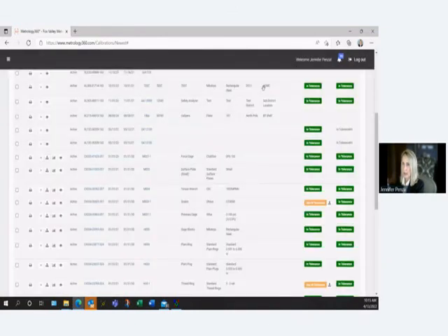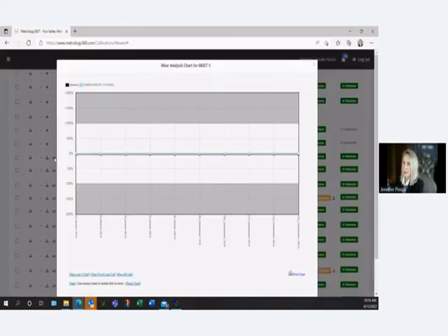The next icon that we have is a traceability icon. I'm sorry, not traceability, a wear analysis icon. The wear analysis icon is really a cool icon if you want to see the progress of how your equipment is being calibrated. You can see the last 3 calibrations here, just the first and the last time it was calibrated, or you can see all the views of your calibrations.